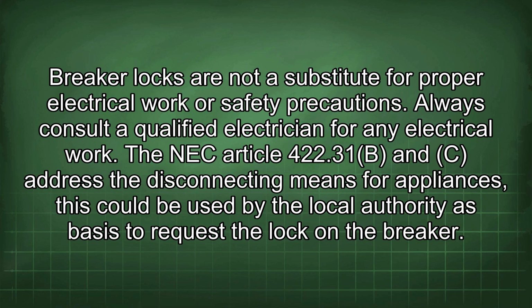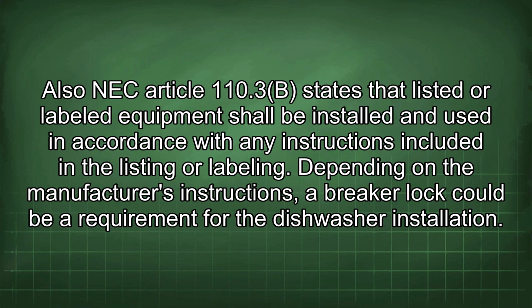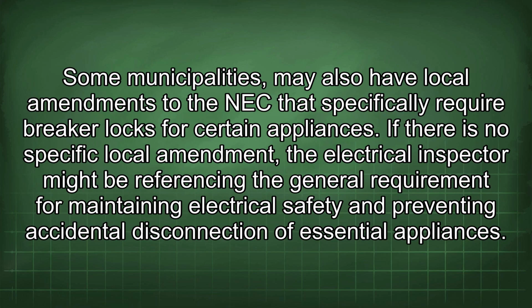The NEC Article 422.31(B) and (C) address the disconnecting means for appliances. This could be used by the local authority as basis to request the lock on the breaker. Also, NEC Article 110.3(B) states that listed or labelled equipment shall be installed and used in accordance with any instructions included in a listing or labelling. Depending on the manufacturer's instructions, a breaker lock could be a requirement for the dishwasher installation. Some municipalities may also have local amendments to the NEC that specifically require breaker locks for certain appliances.